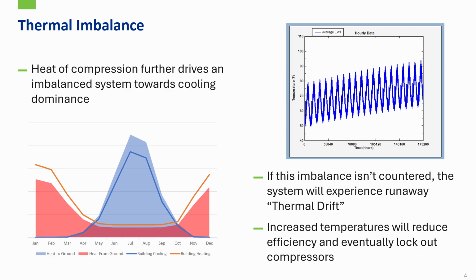The reason that's a problem is that, year over year, ground temperature won't stay constant. You'll get what we call thermal drift, or runaway, which will negatively impact your heat pump efficiencies, and if you let it go on too long, it can lock out your compressors.